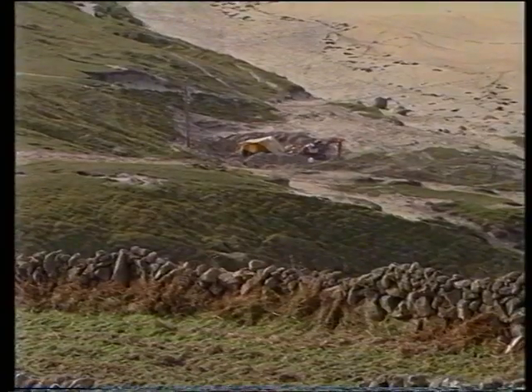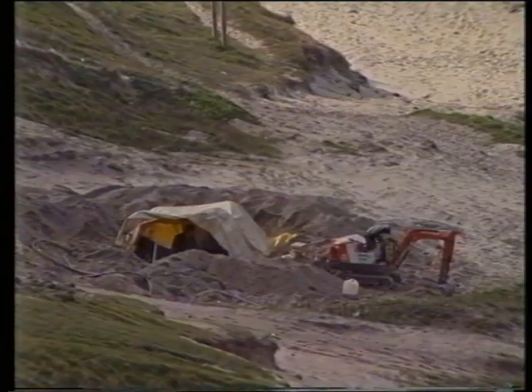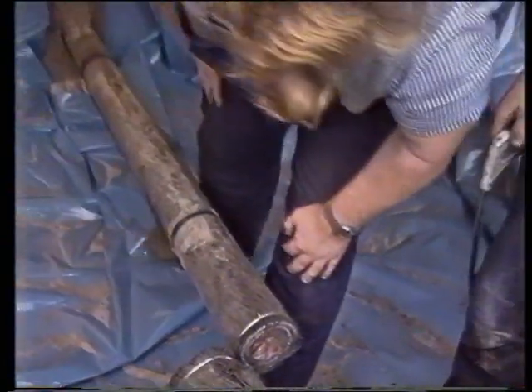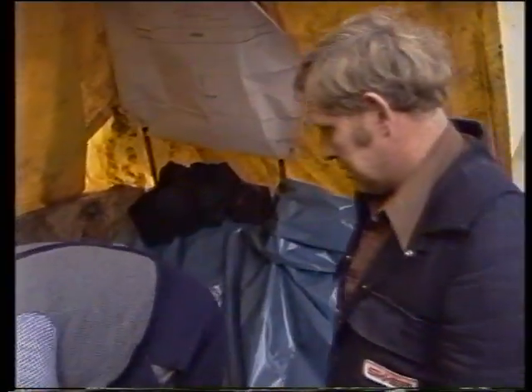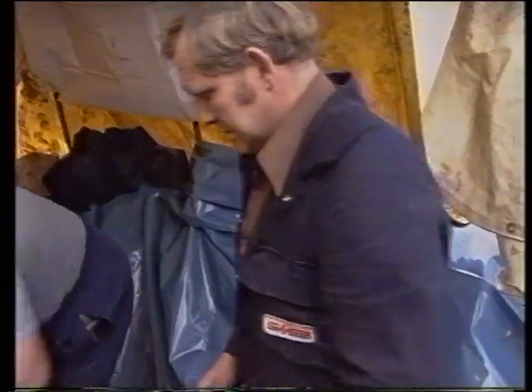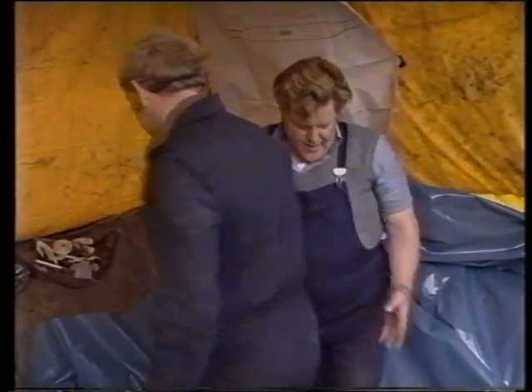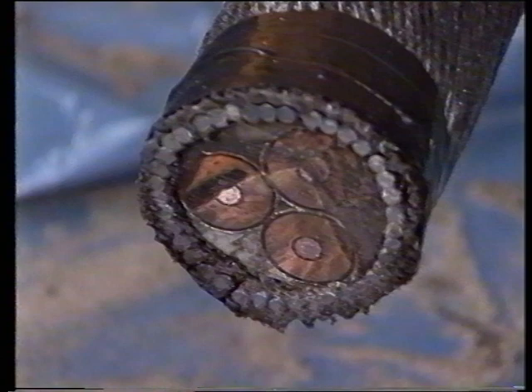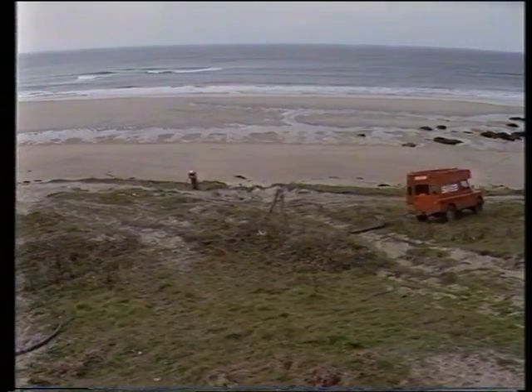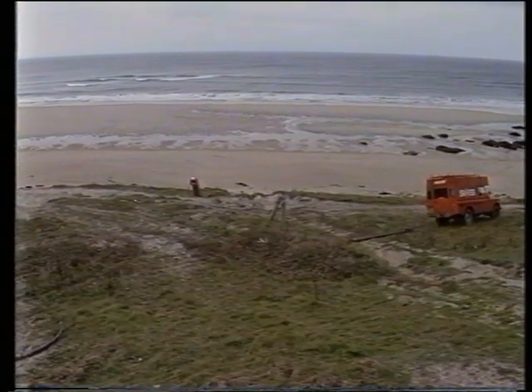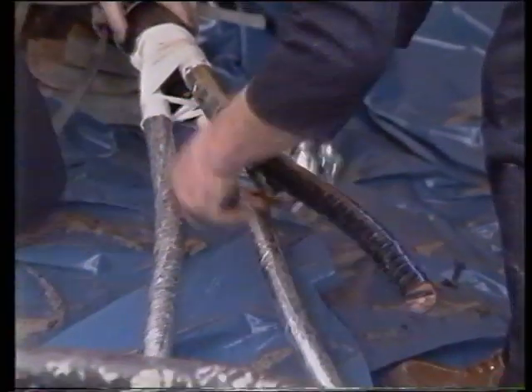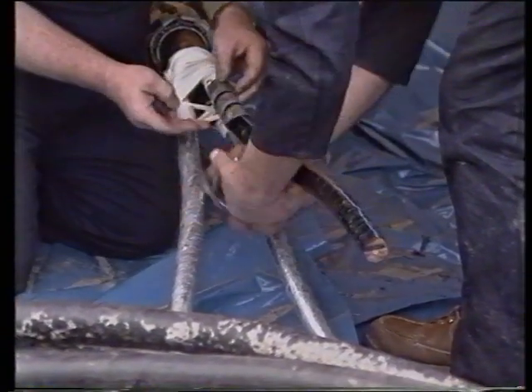On the beach, a strange tent-like structure has appeared. This is where the all-important joint linking the land and sea cables is to be made. First, the submarine cable is cut to length, and cutting through that steel wire armour is no easy task. Great. With the cable the exact length required and the excess towed off out of the way, the jointer and his mate peel the armouring and the screening off the 3 cores, stripping them back to the insulation, ready for the joints to be made.